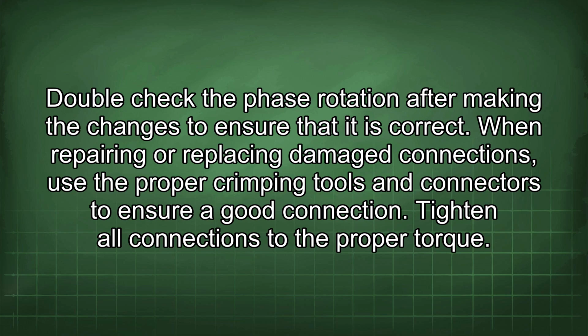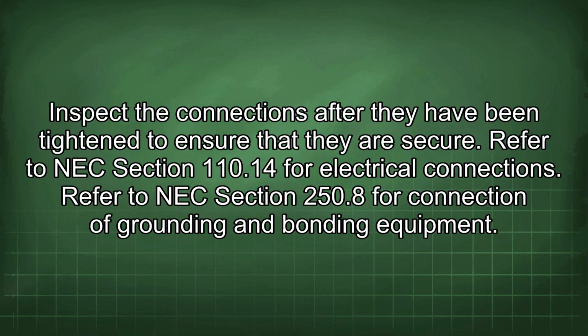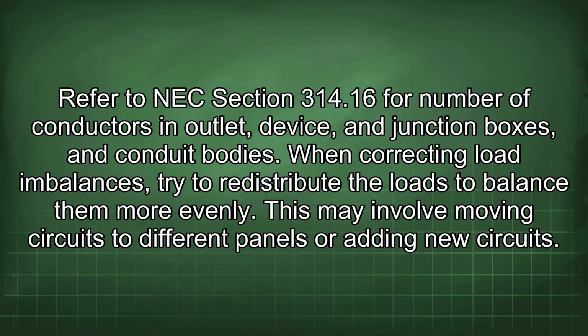When repairing or replacing damaged connections, use the proper crimping tools and connectors to ensure a good connection. Tighten all connections to the proper torque. Inspect the connections after they have been tightened to ensure that they are secure. Refer to NEC section 110.14 for electrical connections. Refer to NEC section 250.8 for connection of grounding and bonding equipment. Refer to NEC section 314.16 for number of conductors in outlet device and junction boxes and conduit bodies.